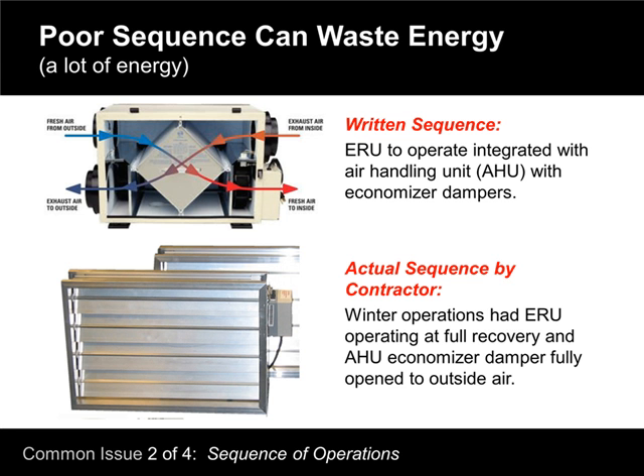Yeah, to me, sequence is related to how components and systems operate together to provide the design intent. So one thing happens after another, and they work their way along the line. You could have dampers that are running for heating and cooling, and they should properly sequence so that you're getting cooling when the outside air is capable of doing that. Instead, you end up with dampers that are opposing each other and not bringing in proper temperature air that can take advantage of some of the design criteria that were put out in the spec.